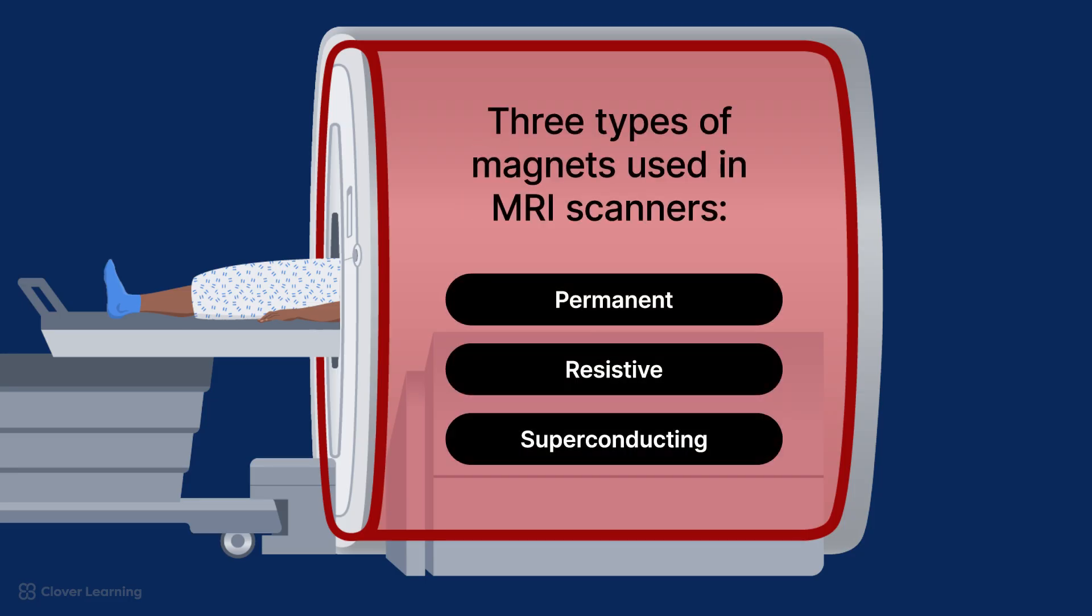The main magnet is the most important component of an MRI scanner. The main magnet creates the strong, uniform magnetic field necessary to create an MRI image. This magnetic field is measured in Tesla, and clinical scanners range in strength from 0.1 Tesla to 7 Tesla. Research scanners can go as high as 45 Tesla. There are three types of magnets used in MRI scanners: permanent, resistive, and superconducting. Superconducting is the most common.